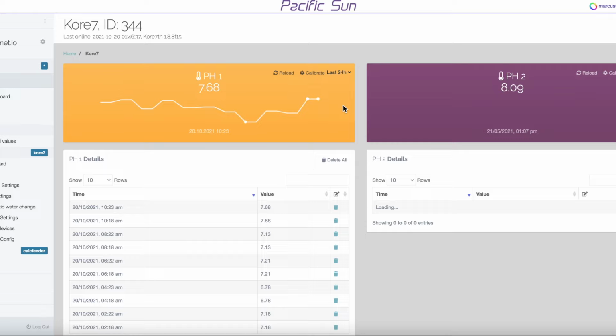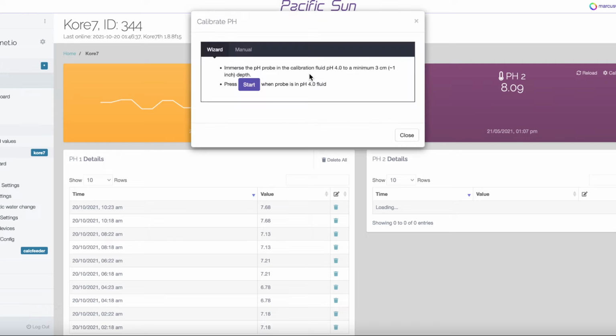So what we're going to do is click the Calibrate button in the top right-hand corner against pH probe 1. And at this point, you have the option of doing it the manual method or the wizard method. I would strongly recommend following the wizard. It just makes it so much easier. So it gives you the clear instructions to immerse the pH probe in the calibration fluid pH 4, and then press the start button when the probe is in the fluid. So let's do that.